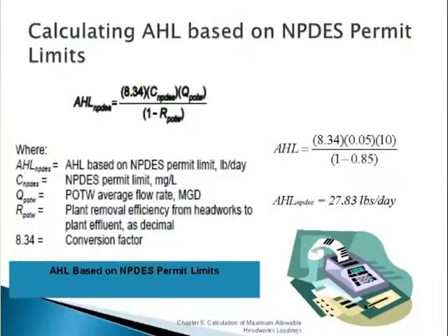Yes. Could you do some sort of a correlation, like with TDS? That's why I thought he did. I thought maybe he did EC and TDS sampling and did a correlation. No, he said, it's a number in the NPDES permit. I just plugged it into this formula. See, that said C NPDES, that's where I plugged it in, and I have pounds of EC. Did he also have pounds per day of pH? No, he didn't do that. 24-hour composite sample. Yeah, so you have to watch out for that. Then it's just, no, you can't do that.